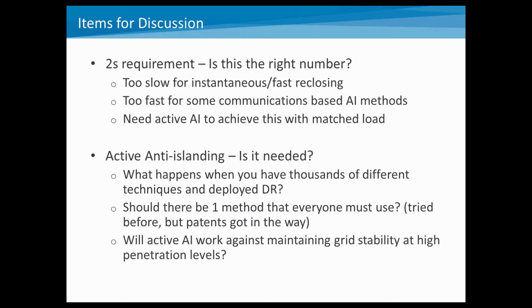Well, in the active anti-islanding world, we actually tried this. Before everybody started patenting all their anti-islanding techniques. Now there's probably 20 different patented anti-islanding techniques out there, and it's probably too late to get that genie back in the bottle. But there may be other permissive ways to have a single method everyone must use. Finally, as we look at higher penetrations of distributed generation, will active anti-islanding work against maintaining grid stability? I mean, the way it works right now is it's actively pushing voltage and frequency outside a normal set point. So on very weak grids, that may actually be detrimental to the long-term deployment of distributed energy technologies.